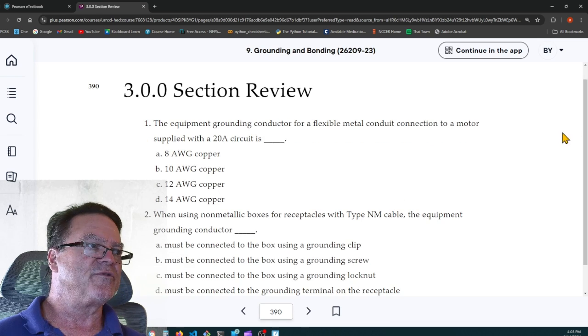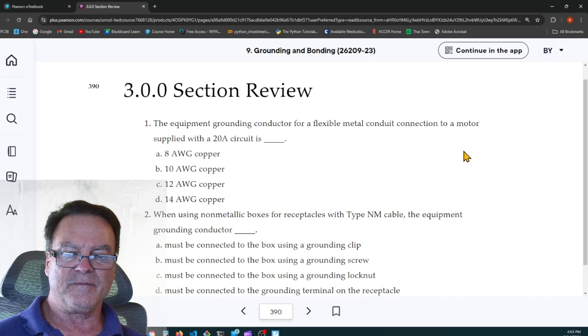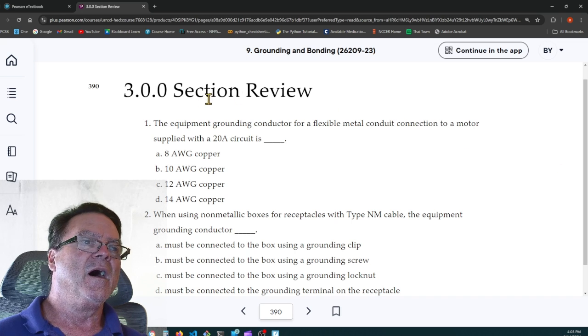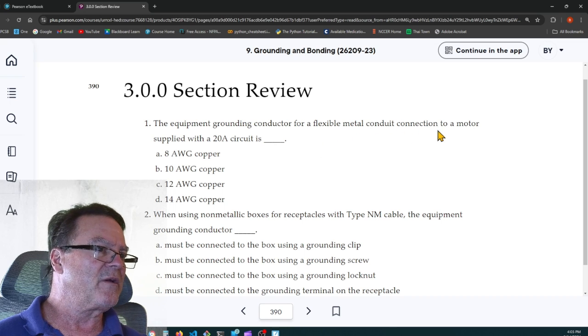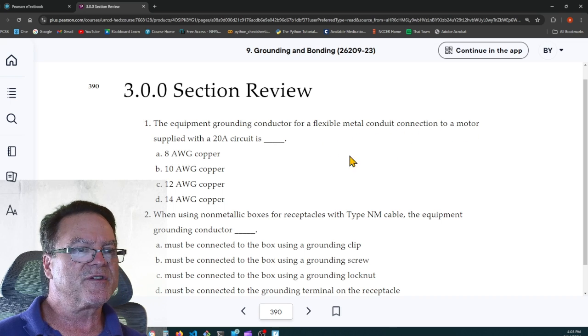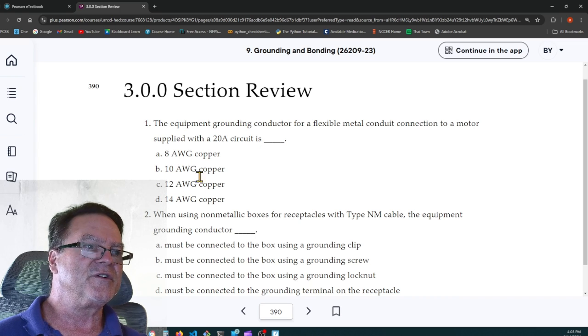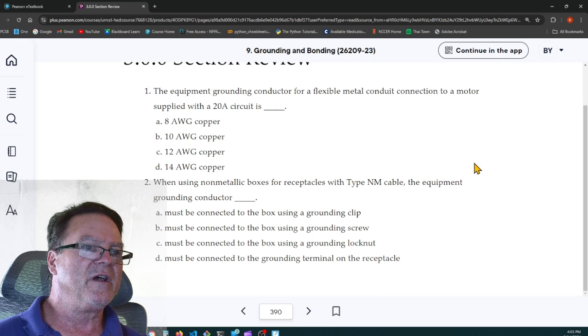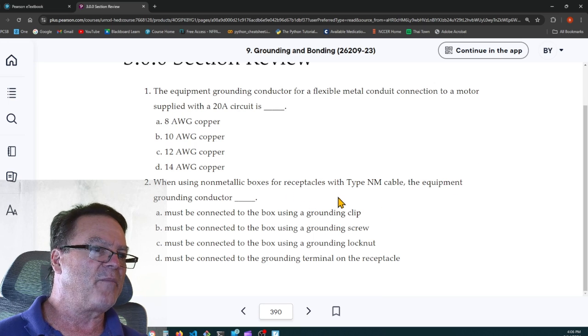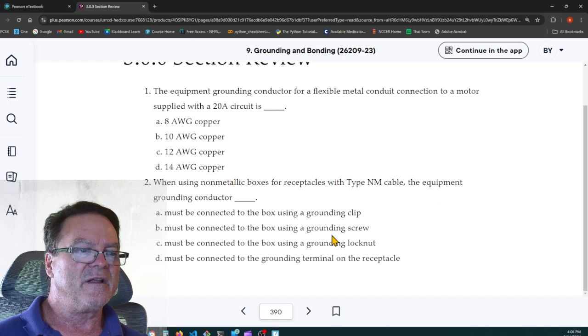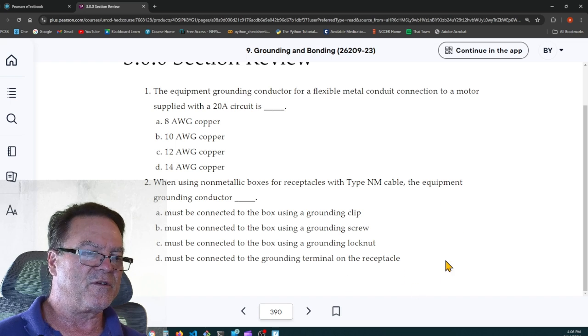And you can use cable tray as an equipment grounding conductor. Section 3 review. The equipment grounding conductor of a flexible metal conduit connection to a motor supplied with a 20 amp circuit is, then you can go and check and see what the size would be. When using non-metallic boxes for receptacles with type NM cable, the equipment grounding conductor, and then you can look that up. We're just looking at that.